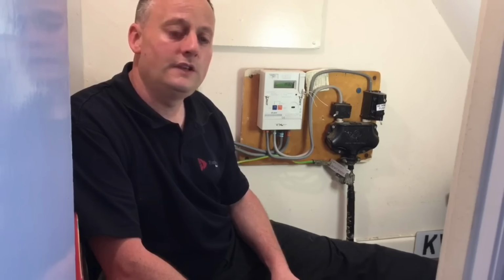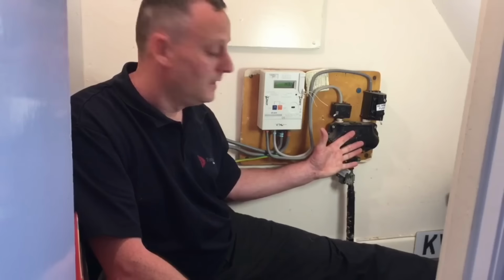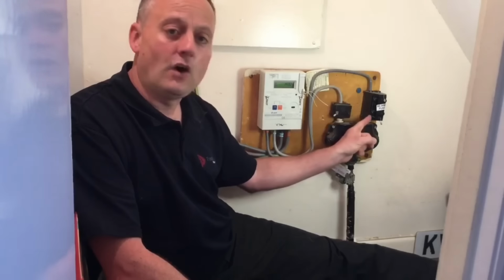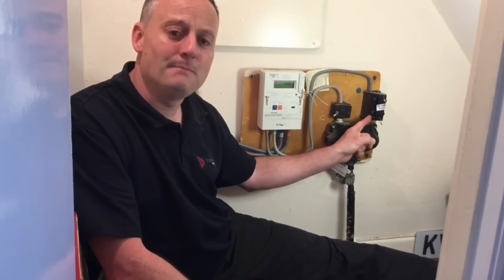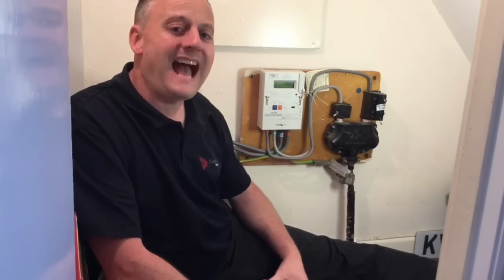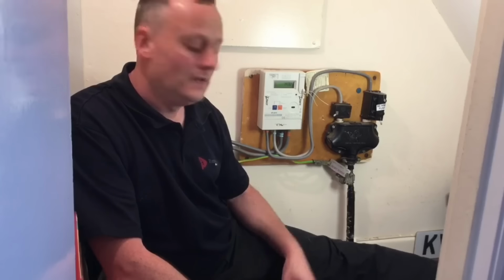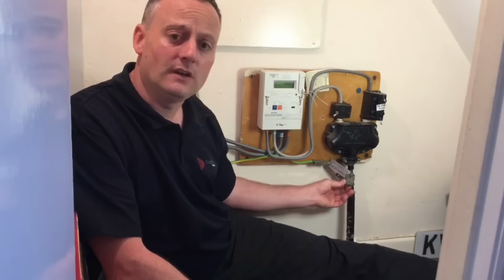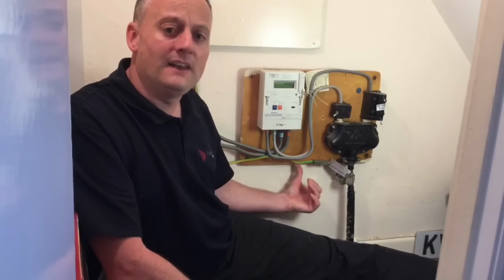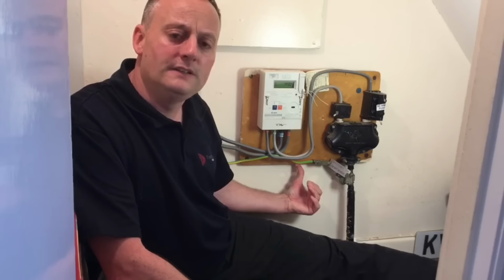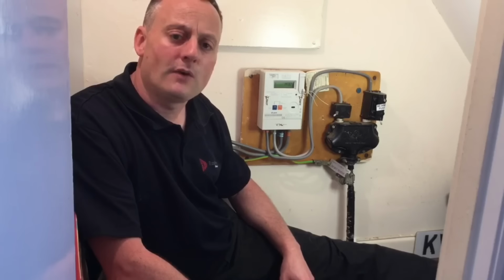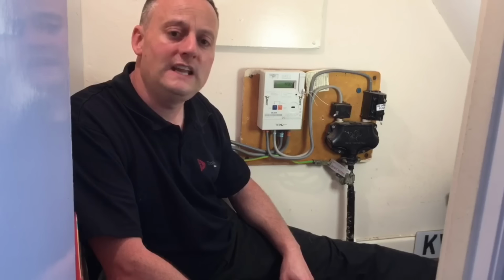So to recap then, the supply authorities have brought in a cable containing 3 conductors. Line and neutral conductors terminated within our cutout, separated for a neutral, and the line going through, in this case, the 60 amp incoming fuse. We're using the outside sheath of the cable to provide us with our earth connection. Okay, so it goes into our MET and then goes out into our 16mm earthing conductor. The incoming supply authorities cable often has lead or steel sheath for that protective conductor. In this case, we're connected to one which is made of steel.